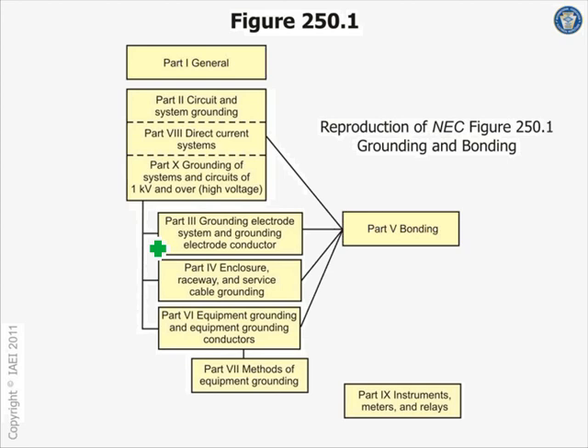Utilities, though, when they come to my house and give me 7200 on that one line and the neutral, they're dealing with that neutral wire that's coming, the grounded wire. That wire is grounded at multiple locations. So anyway, they talk about it here. Grounding electrode system and conductors, we just touched on that one right in here. Enclosures, raceways grounding, guys, especially at the service in this section. Equipment, when they say equipment, they mean equipment other than the service, downstream. That's in this section. And of course, bonding, can you guys see bonding goes with all of them? Bonding goes with all of them.